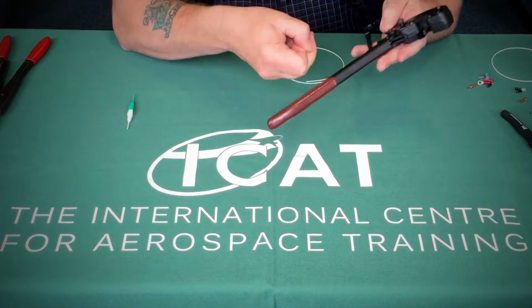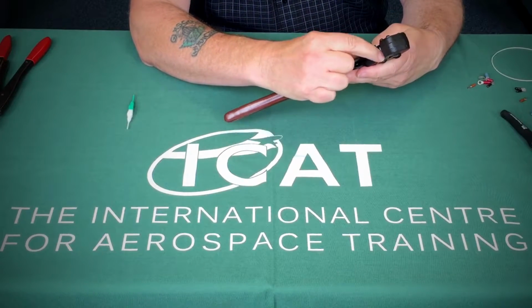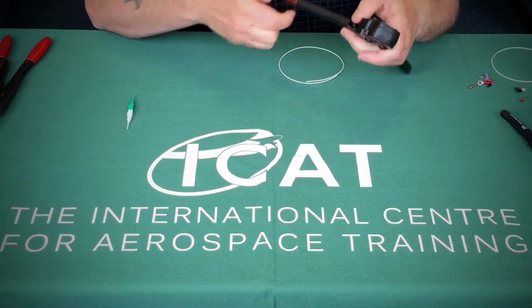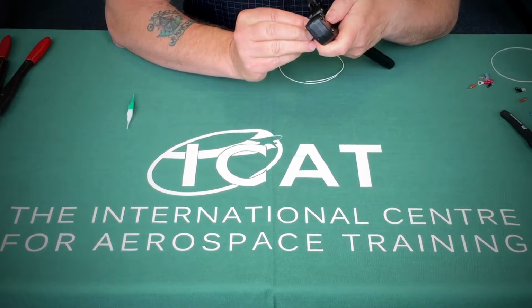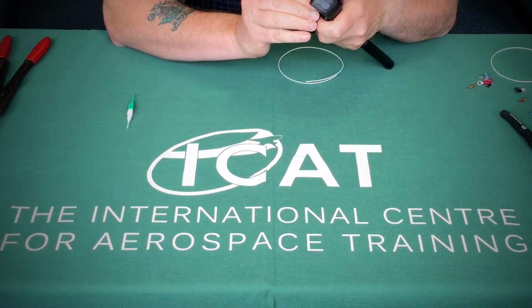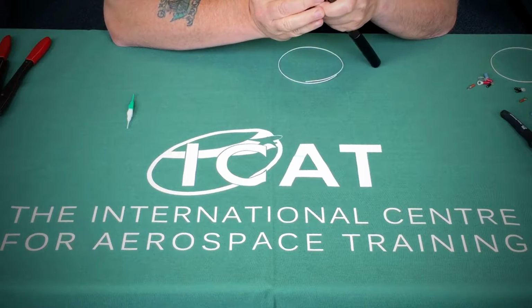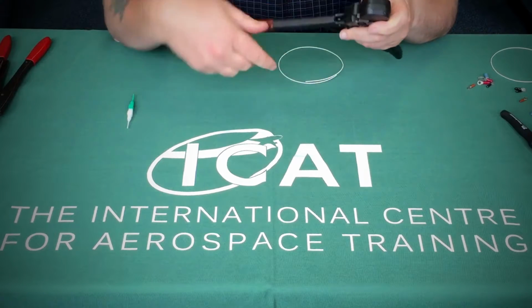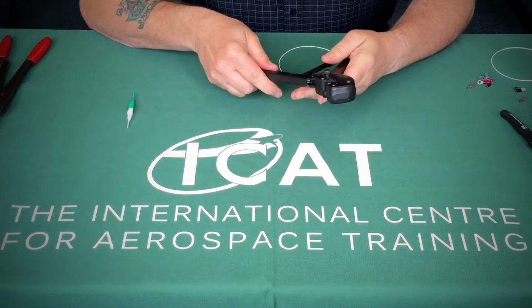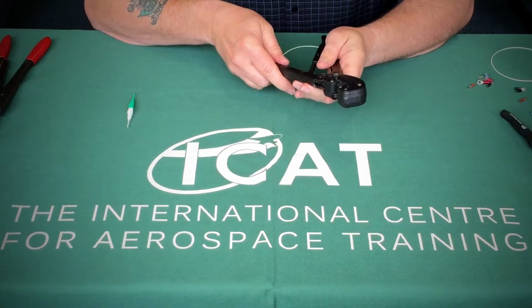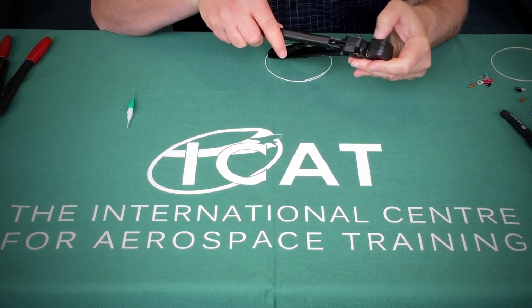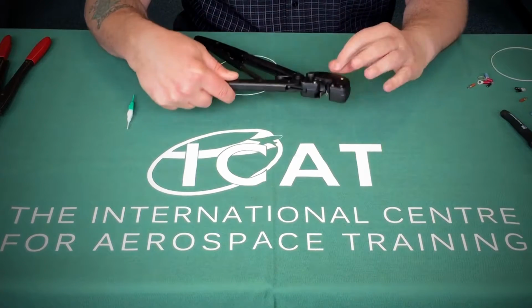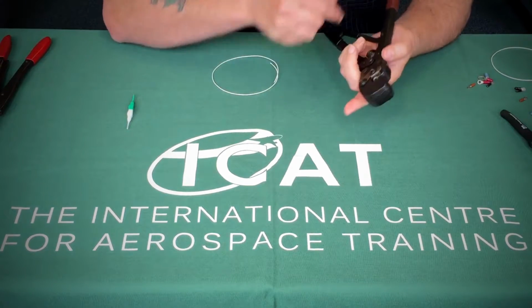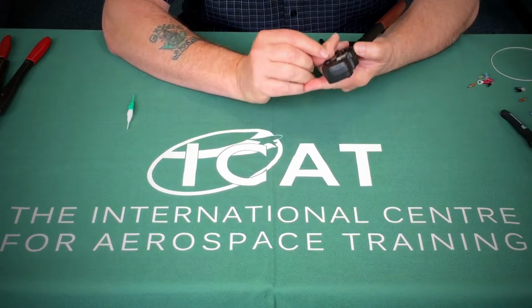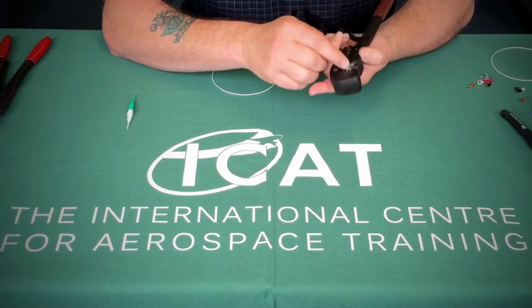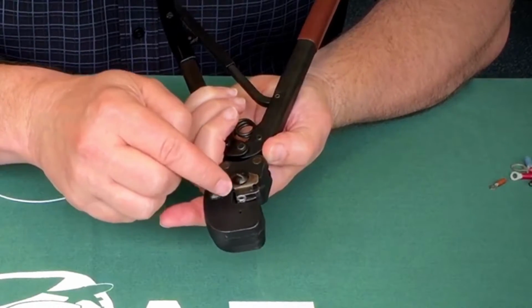The little locator is on a little spring, so that will move up and down. It's not that simple to do, so you just fiddle with it and you place the crimp into the tool itself. When it's in, you can very slowly close the jaws to make sure it's correctly aligned. It should be flush with the front of the tool, and you should be able to check the connector is sitting nicely over the locator at the back of the tool, as shown here.